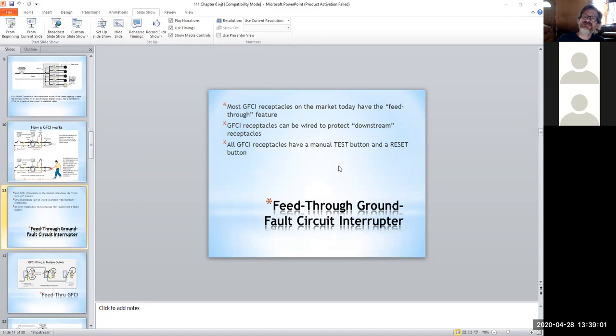They all have a test and reset button now, and what they call in the top bullet item the feed-through feature, which is the line and load I was mentioning. You go in the back, and they look similar to a receptacle, but you'll see in the back where the upper portion is labeled line and the bottom portion is labeled load, and they're separated. The line side is literally where you'd come from the circuit breaker in the panel and wire it up, and then the load would feed other receptacles down the line, so they get protected by the GFI as well.